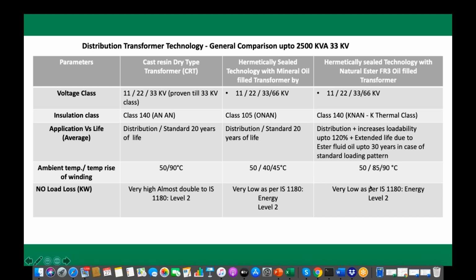Proven studies or analysis are not there, but because of the process complications, normally the dry type transformer life is calculated as 20 years. In a distribution transformer, a conventional mineral oil life is calculated as 22 or 20 point something based on the IEEE formula, whereas this is purely coming from one of the American utilities. They have disclosed a lot of calculations and published some international papers on life assessment on their network. And for K class fluid transformers, which use natural ester, this data is from natural ester FR3. Those are normally 33 years of life. That's how they say you extend life by 1.5 times.